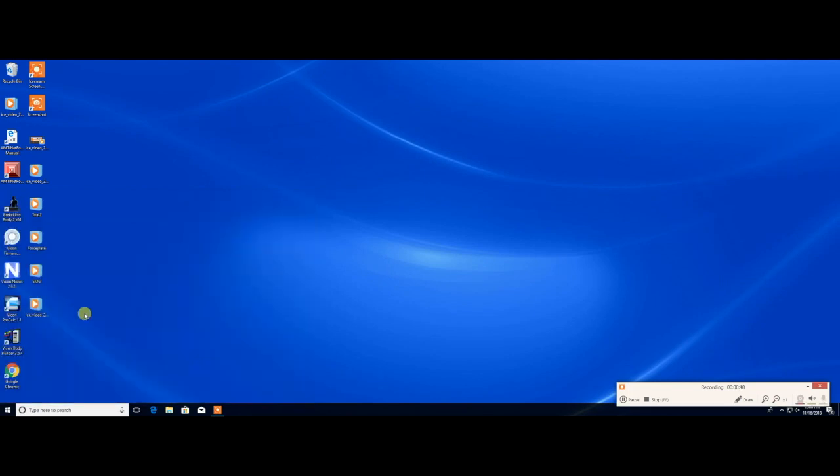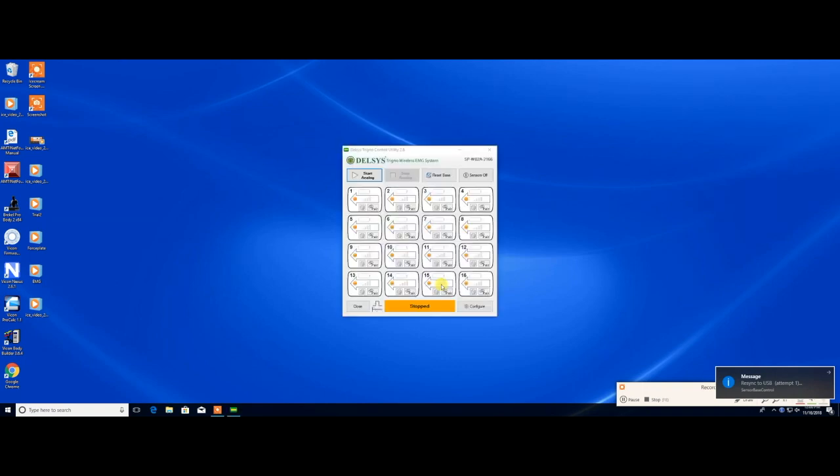First, go to the Windows tab, scroll up to the DELSYS-Inc tab, and open the DELSYS-Control utility from the drop-down menu. This must be opened before collecting EMG data through the Vicon program. Opening the DELSYS-Control utility resets the base station. When the control utility opens, you will see that each EMG sensor is shown along with its status. If the sensors are not paired upon opening the control panel, you can pair them by clicking on the round power button located on each sensor. This will cause the yellow status light to turn green, indicating that the sensor is paired.